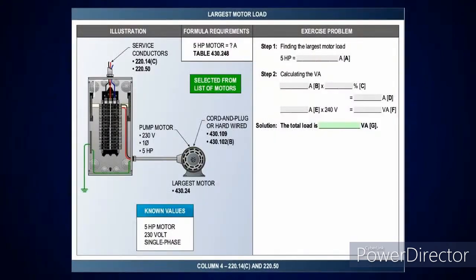Okay. So here's one here. We're showing you a 5 horsepower single phase 230 volt motor. Get the amperage, take it at 125%, and that'll give your amperage. Take it at 240 volts, and that'll give you your total load for your additional VA.